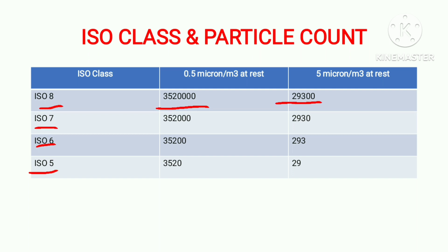Similarly, for ISO 7 it is 352,000 for 0.5 micron and 2,930 for 5 micron. For ISO 6 it is 35,200 and 293 for 5 micron. For ISO 5 it is 3,520 for 0.5 micron and 29 for 5 micron.